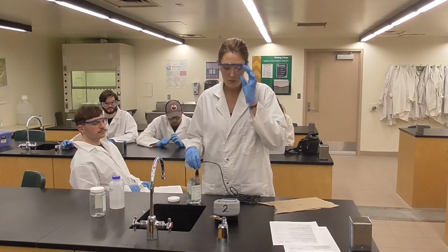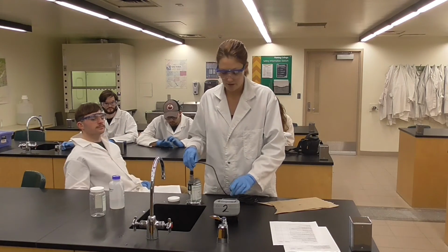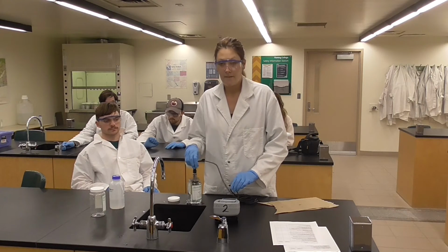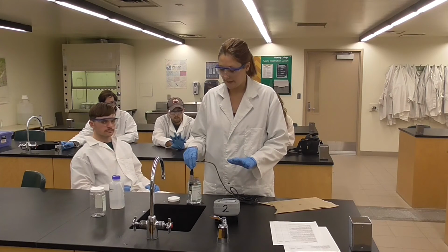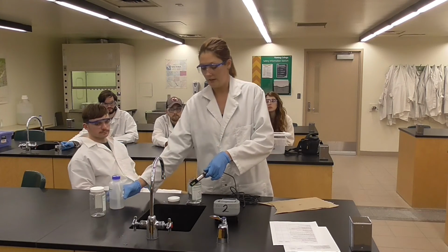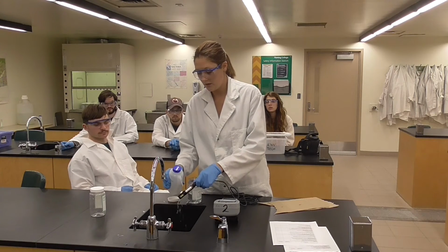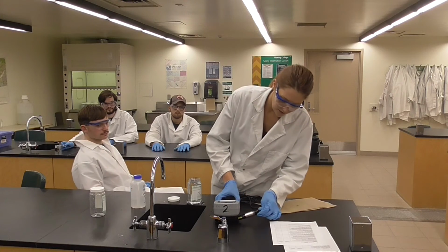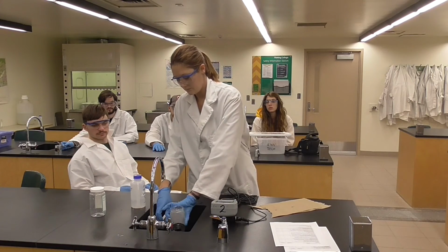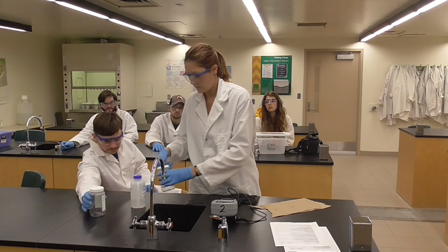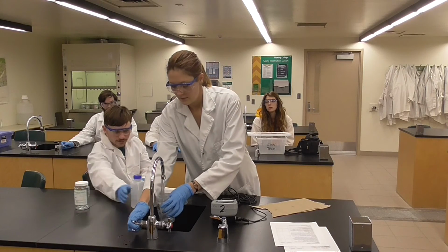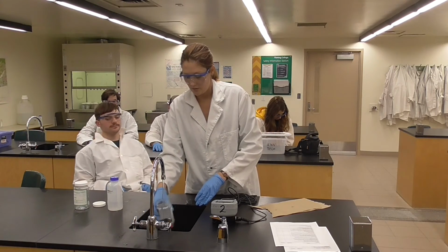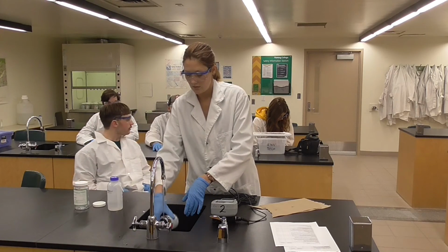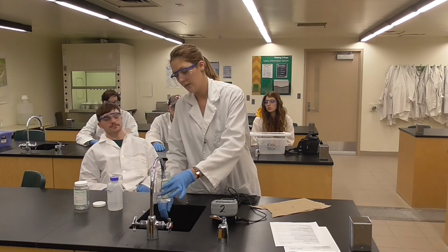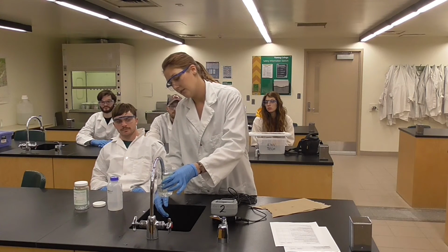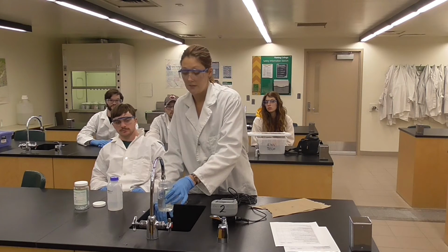Then we press enter. And now it comes up asking for the salinity, so this is fresh water, so we're just going to keep that at 0, and enter. And now this meter has been calibrated and we are good to go and test this with another sample. So I'm just going to rinse this off with distilled water here. And we can just set this here until we're ready to test. I'm just going to triple rinse this. And then, same as in part 1, we want to be careful that there's little headspace on this. No headspace on this, actually.